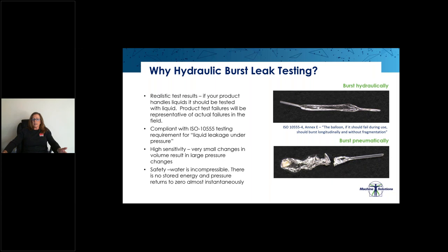Product failures during testing will be representative of actual failures in the field hydraulically. Another reason is for regulatory compliance. ISO 10555 calls for liquid leakage under pressure. Hydraulic testing tends to be more sensitive than pneumatic testing, and very small changes in volume result in large pressure changes, making leak detection more sensitive.